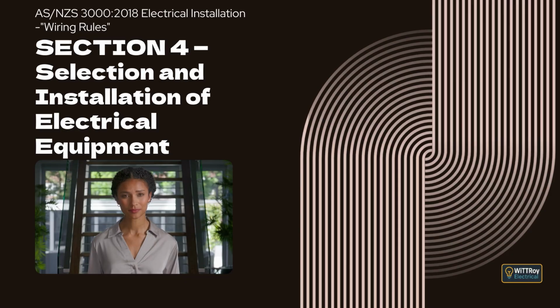Clause 4.18.1.3 In New Zealand only. In New Zealand installations, a gas appliance must be provided with a means of electrical isolation using either a plug connected to an accessible switched socket outlet, a plug connected to a socket outlet that may be inaccessible but controlled by a separate accessible switch operating in all active conductors, or an accessible lockable isolating switch operating in all active conductors. Clause 4.18.2 Gas cylinders containing heavier than air gases outdoors.